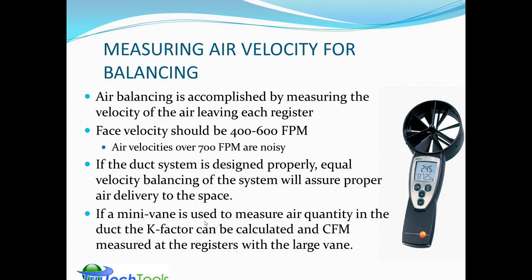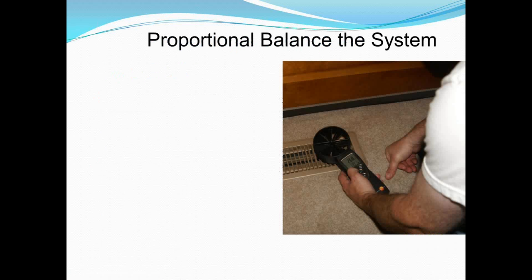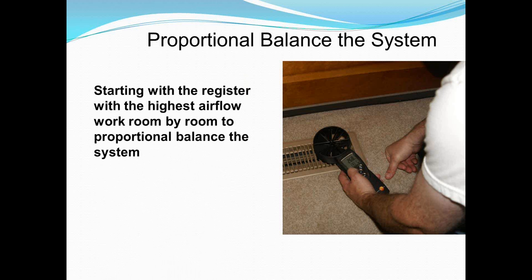There's also a technique using the mini-vane to measure in-duct airflow and the large vane at one terminal. If all the supply grills are the same type, you can compare the duct flow measurement to the sum of the terminal flows to calculate the K factor of the register. This is proportional balancing — using the Testo 417 large vane rotating anemometer (approximately $450), starting with the register that has the highest airflow and working room by room to ensure airflows are proportional to the loads.